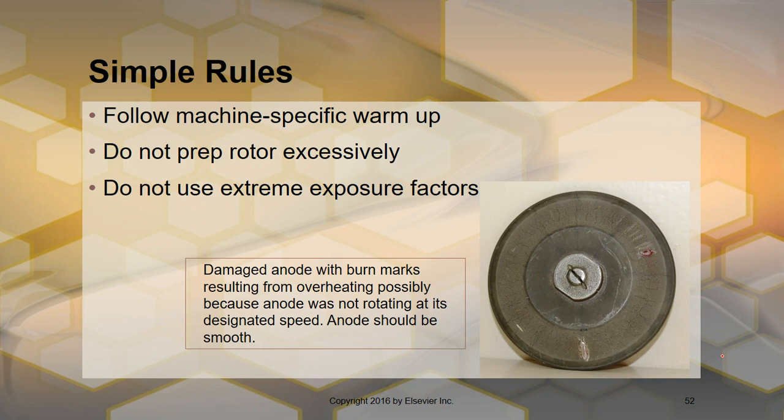We have talked about the X-ray tube, the housing that the tube's in. We've talked about the anode. We talked about the cathode. We talked about how everything works. To extend tube life, simple procedures and guidelines should be followed. If the machine that you're working at, and you'll see this in clinical, has warm-up steps, that's specific to the unit, and you should follow them completely and routinely.